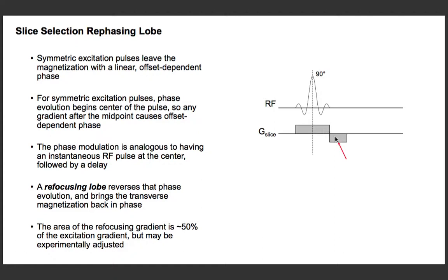It's important when you're doing gradient dephasing to have the area of the gradient dephasing lobe be 50%, so it's going to match the second half of that RF pulse. If you had a more complicated RF pulse, like something asymmetric, for example, which you can do, you might need to experimentally or numerically calculate what the area ratio is to cause complete dephasing, because as you'll see in a second, this gradient will cause some spread out of the frequency, and this just corrects that amount.